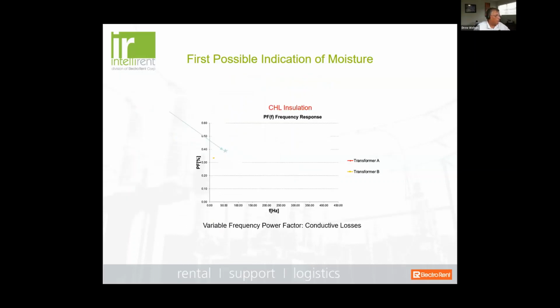Okay, so how do we first determine if we could possibly have moisture? Well, the first thing we're going to do is a power factor test, okay? And if we do our power factor at 60 hertz, a CHL may show a slight rise in power factor measurement if you have excessive moisture. However, it's hard to determine whether that's moisture or just natural aging of the overall insulating system, which could occur. But what we've learned in the industry is that if you do what's called variable frequency power factor testing, you will see here that you may have elevated power factor in the low frequency range versus lower power factor. And we want to look at this angle because what this could indicate is that what you have shown here are what we call conductive losses.